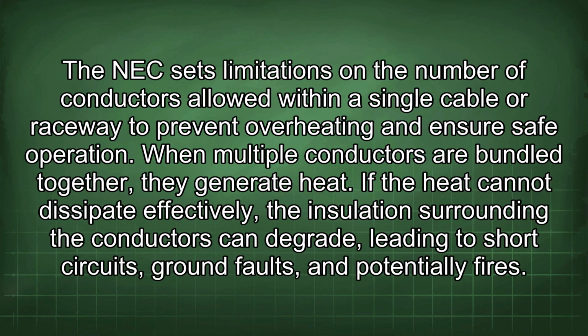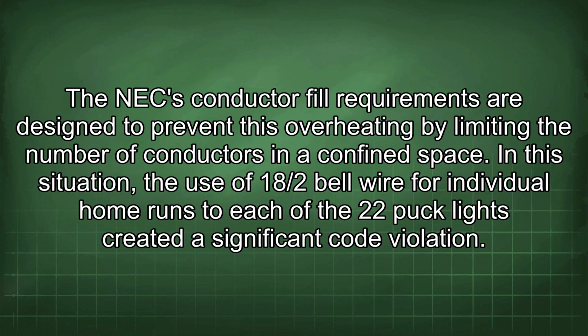The NEC sets limitations on the number of conductors allowed within a single cable or raceway to prevent overheating and ensure safe operation. When multiple conductors are bundled together, they generate heat. If the heat cannot dissipate effectively, the insulation surrounding the conductors can degrade, leading to short circuits, ground faults, and potentially fires.